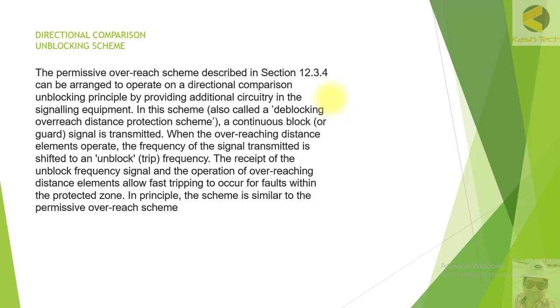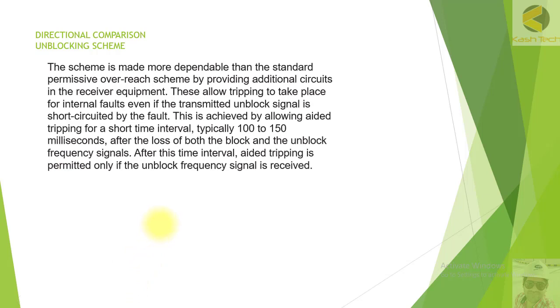In earlier implementations using power line carriers, a guard frequency continuously blocked the relay from operating. As soon as the remote end does not see a fault in the reverse direction, this blocking is removed and the relay can operate. The scheme is made more dependable by allowing tripping to occur for internal faults even if the transmitted unblocked signal is short-circuited by the fault — achieved by allowing aided tripping for a short time interval, typically 100 to 150 milliseconds, after the loss of both block and unblocked frequency signals.